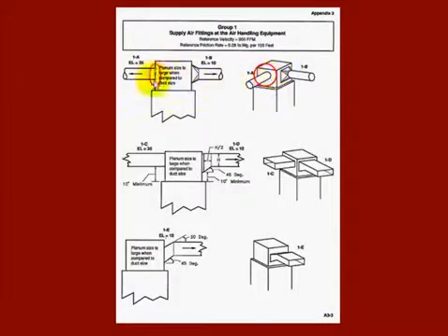This is the isometric view, of course. Now, this is a typical flat collar we all know and love. And I don't recommend taking branch lines off of plenums, but this will serve the purpose. What you will see here, they're going to call this a 1-A fitting. That doesn't matter. What matters is the EL, the equivalent or effective length, is 35 feet.